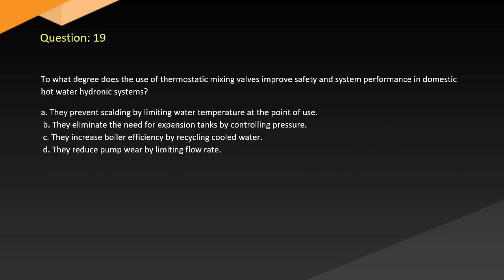Question 19. To what degree does the use of thermostatic mixing valves improve safety and system performance in domestic hot water hydronic systems? A. They prevent scalding by limiting water temperature at the point of use. B. They eliminate the need for expansion tanks by controlling pressure. C. They increase boiler efficiency by recycling cooled water. D. They reduce pump wear by limiting flow rate.